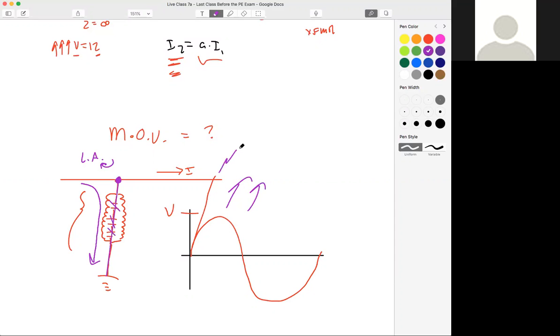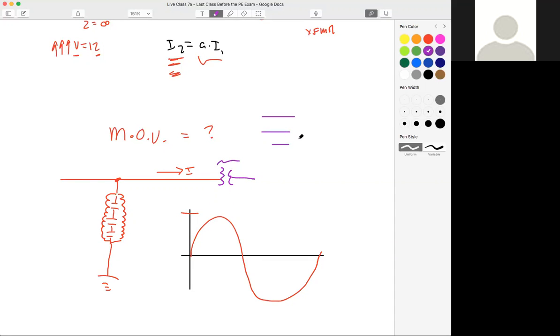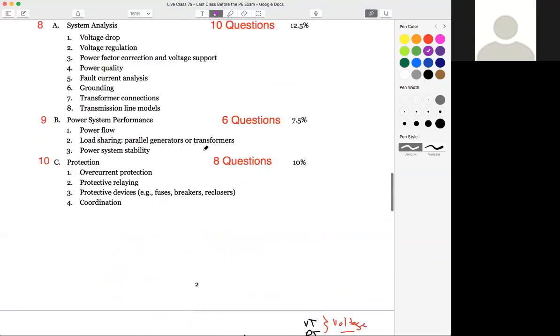And as soon as that crazy voltage transient goes back to normal from our lightning strike, what happens? Then they open, and our current goes back to flowing down the line. It's pretty cool. You see them in the industry a lot before substation transformers. If you have a really long run of lines to the middle of nowhere and then a small sub, you might see them right before that substation just to protect it.